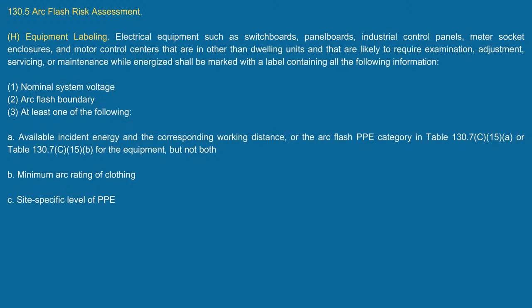But now look at what we require here in the 70E document. We want to know what is the system voltage. We want to know what the arc flash boundary is, and then you need to put in one of the following here. You need to have the available incident energy and the corresponding working distance. Okay, well, if I look at the available incident energy, that's going to be in compliance looking at 110.24A and B of the National Electrical Code, which is going to get into your short circuit current or available fault current, whatever you want to call it, and then you need the working distance.